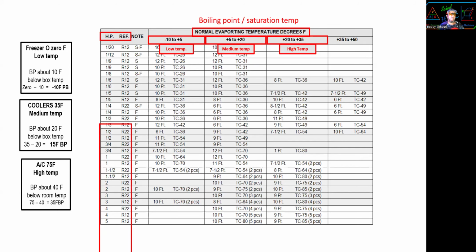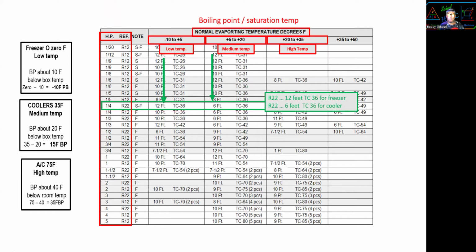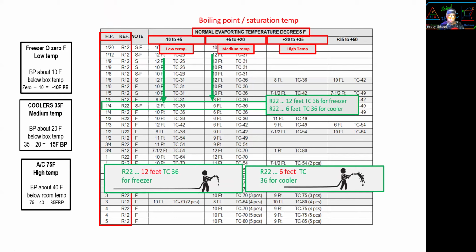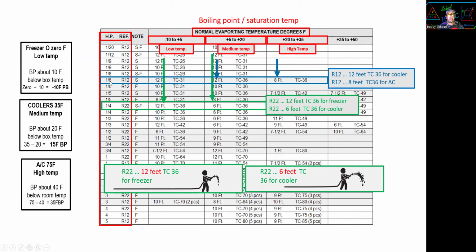All right, now let's go back to the capillary tube. On this chart, this is how to size it. We've got to know the horsepower and the refrigerant. Example, quarter horse R22. For low temp we need 12 feet of size TC36, and 6 feet of size TC36 for medium temp. As you can see, the freezer needs longer, more pressure drop. Cooler, same exact diameter cap tube, shorter, less pressure drop, because the evaporator for the freezer runs colder than the evaporator for the cooler. Example number 2, R12, 1/6 horsepower, that's a small one, 12 feet for cooler, but 8 feet for AC.